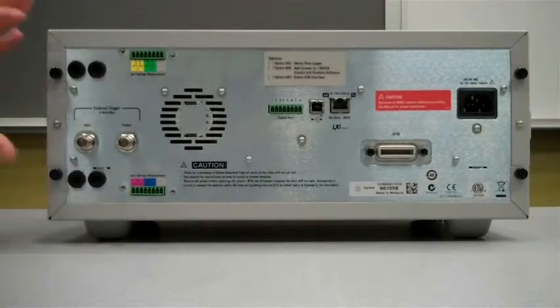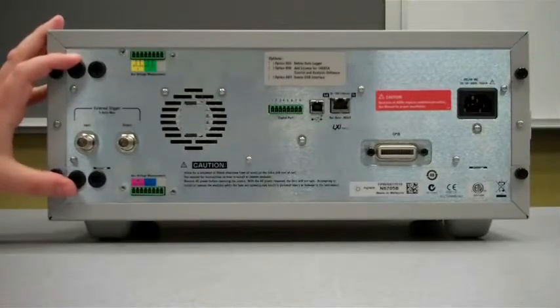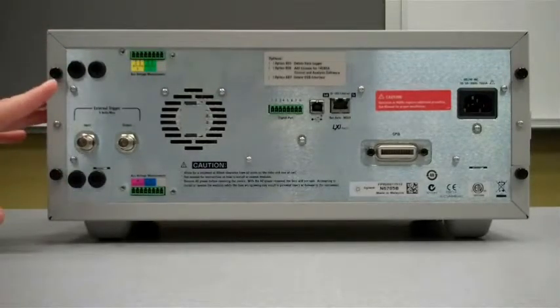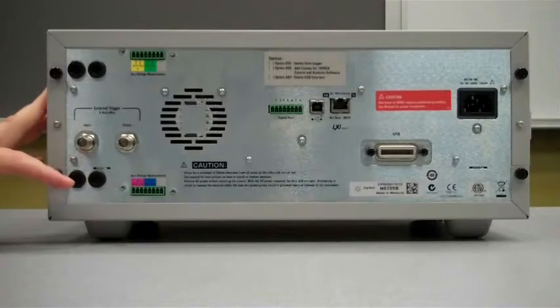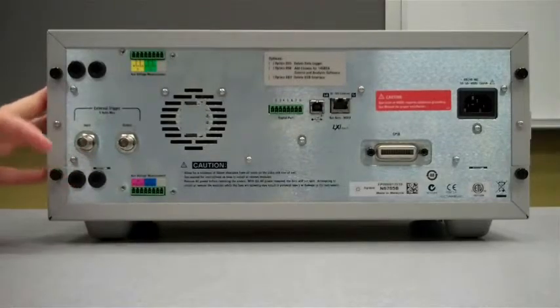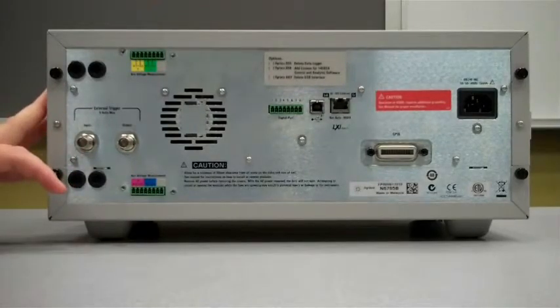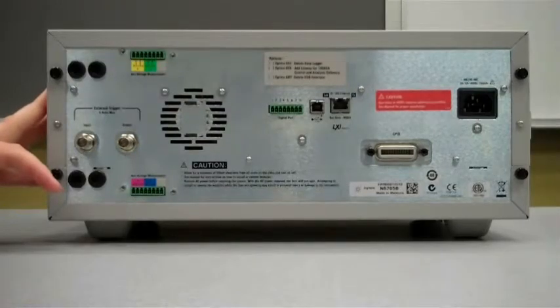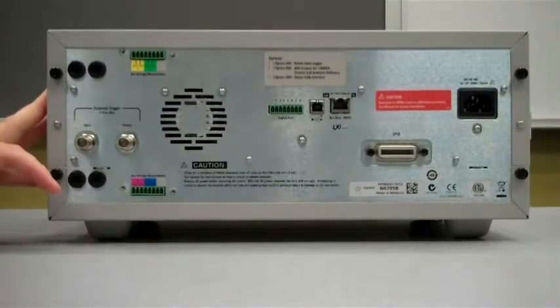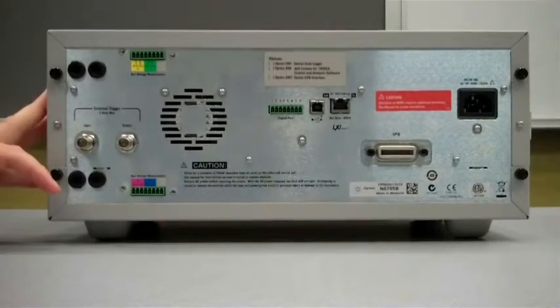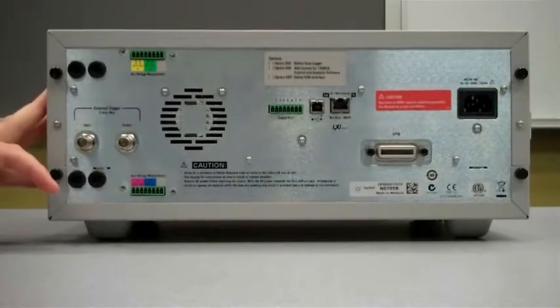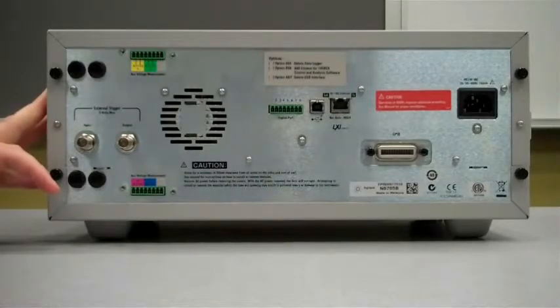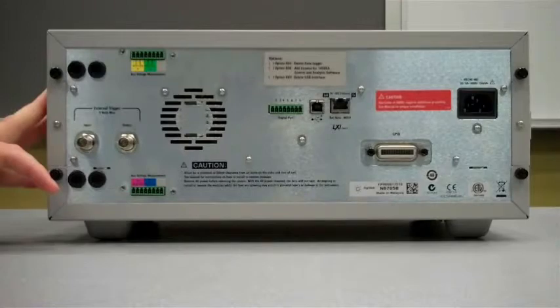The openings are so that you can run wire from the module out the rear of the unit. This is useful for rack mounting. If you have it in a rack, you don't want wires going around to the front. It's also imperative that you use these openings for the N6753A module. The front panel binding posts are not rated to do 50 amperes. To do 50 amperes, you have to use these rear openings.